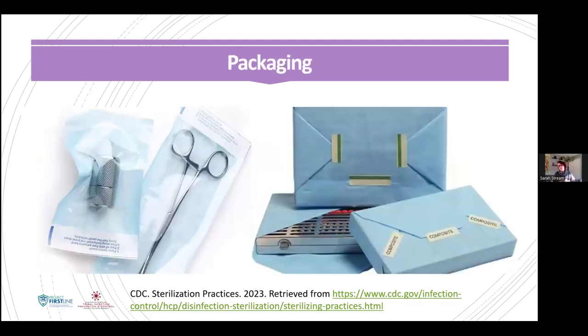Packaging the instruments. We really want to make sure those instruments are thoroughly dried. If you have wet instruments in wet packages going into a sterilizer, you're going to have wet packs coming out. So make sure all the instruments are dried, and then whatever packaging you're going to use is really dependent on the facility needs. So if you're using loose instruments versus cassettes, you may use pouches versus the blue wrap. It really just kind of depends on what's going on in your office.